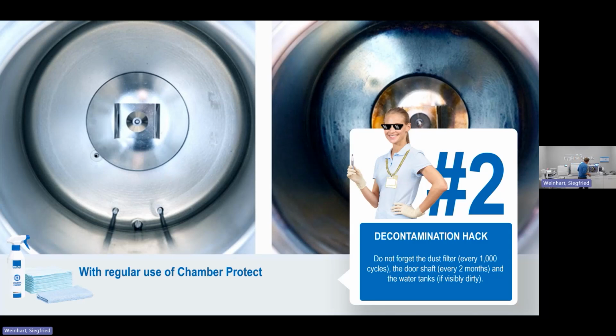Don't forget also with things like these, you've got dust filters. So look at this one. Okay, your units may well have dust filters. Most dust filters need to be changed after a duration of time, which the units will tell you. Okay, so this unit is 1,000 cycles, so always look at the dust filters as well.